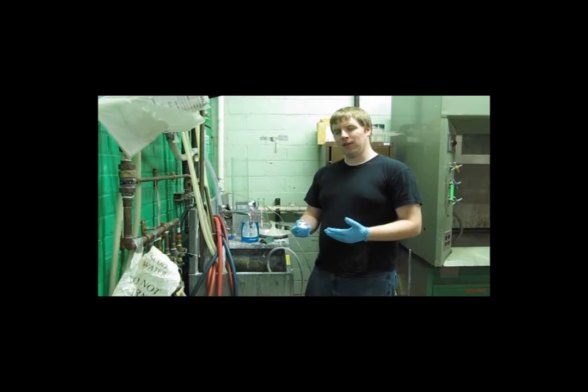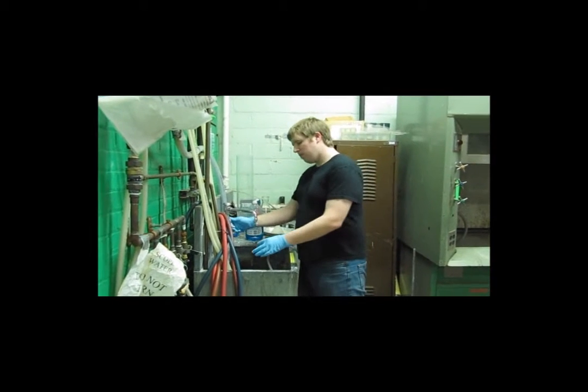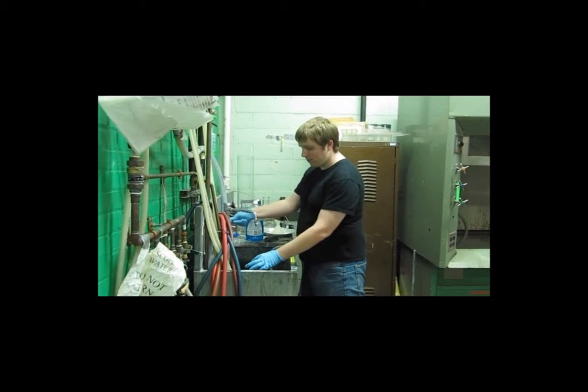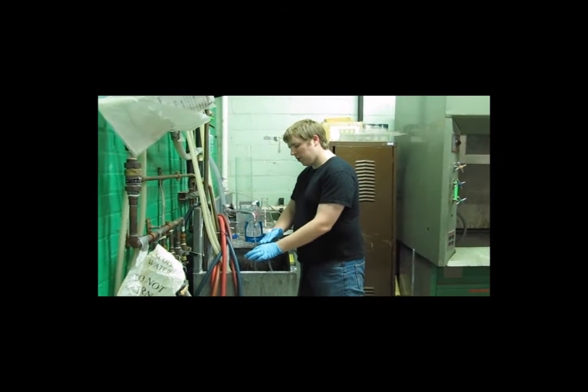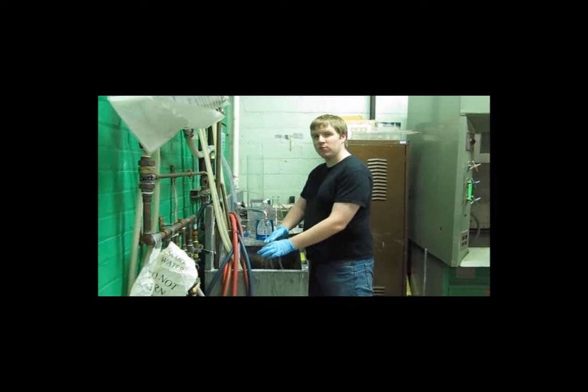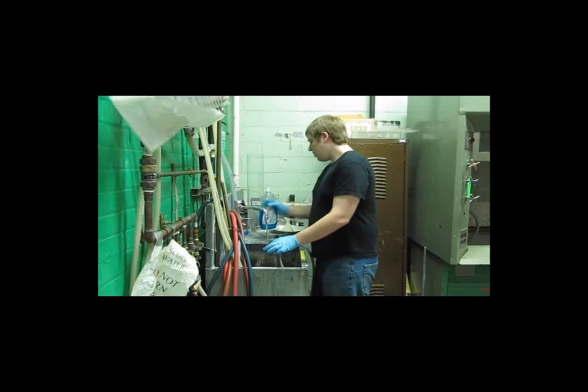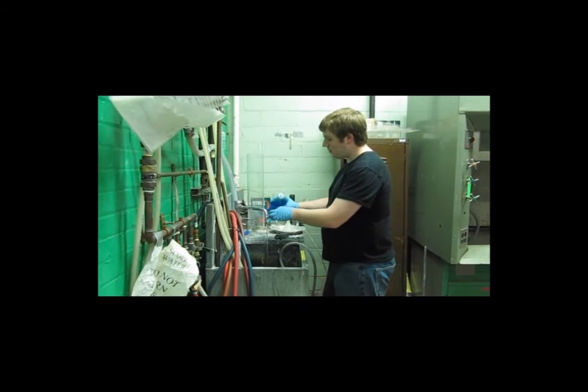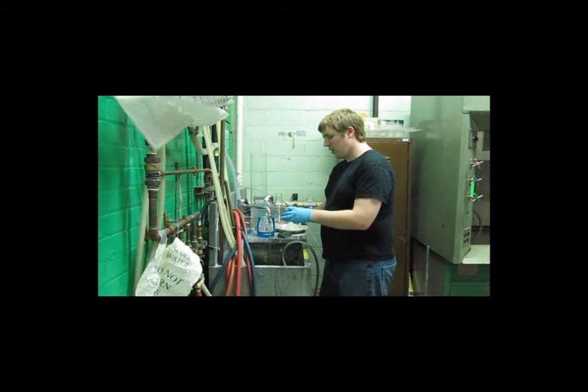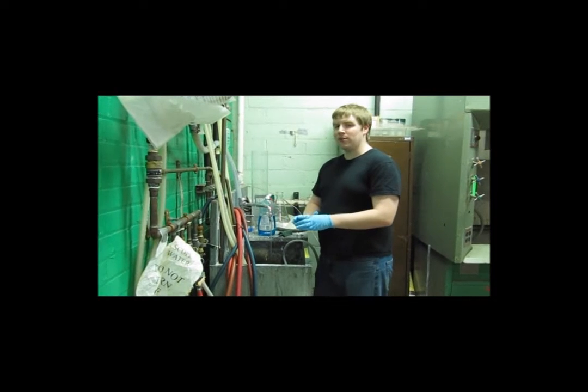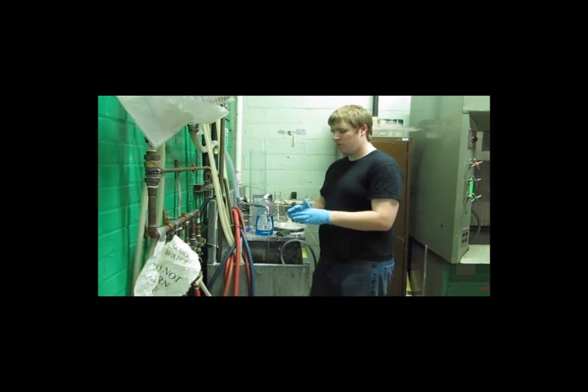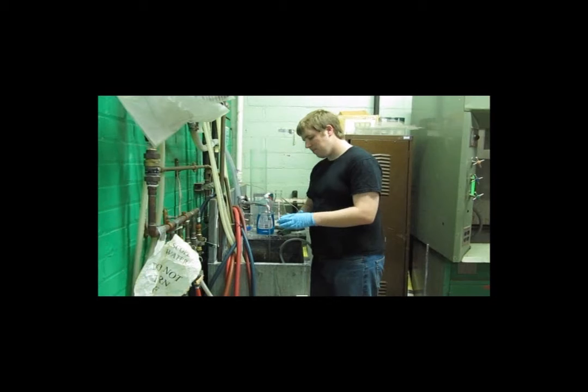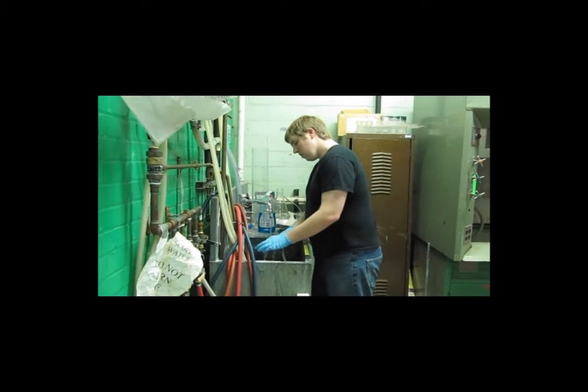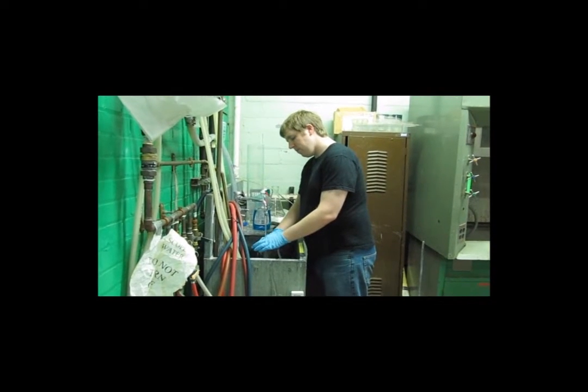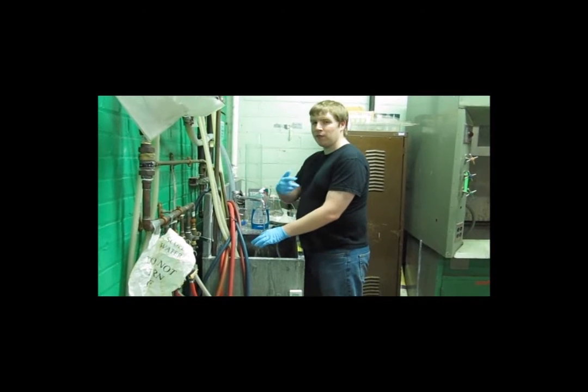After we've sanded the electrode, we bring it over to this station, where we rinse it off in just regular tap water first, to remove any sort of aluminum dust that may have stuck to the surface while we sand it. We have a little bit of Dawn soap from the top, and gently work it out. This should remove most of the contaminants that might have been stuck on the surface from previous uses. Rinse it off very thoroughly.